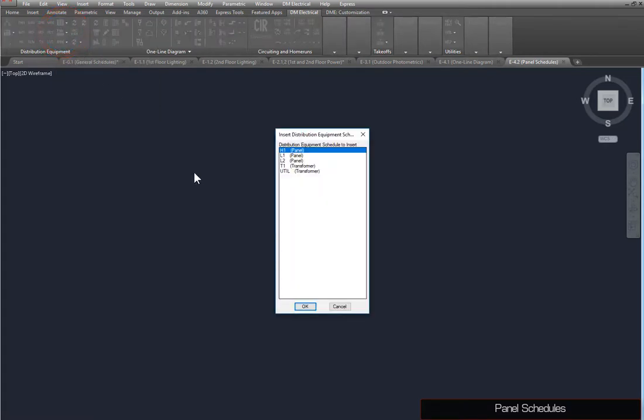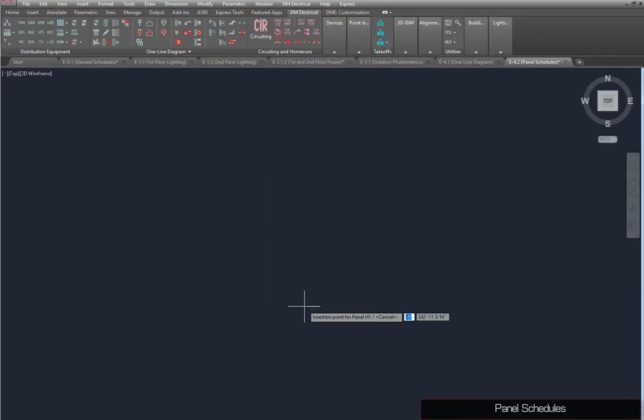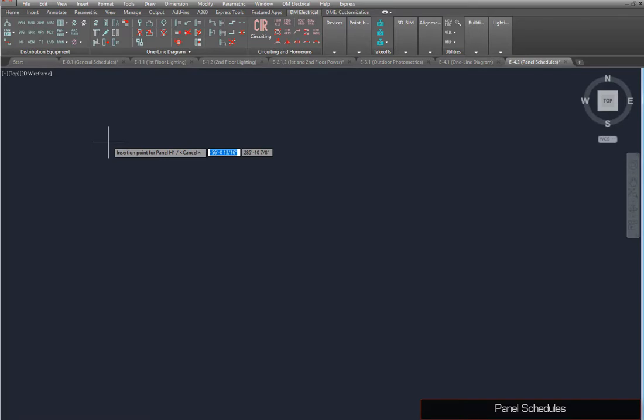Panel schedules in Design Master Electrical are connected to the project database, and will update as changes are made. This connection also allows you to place panel schedules on separate drawings. Run the Insert Distribution Equipment Schedule command. Select H1 and press the OK button. You will be prompted to specify a location on the drawing. The top left corner of the panel schedule will be inserted at this point.